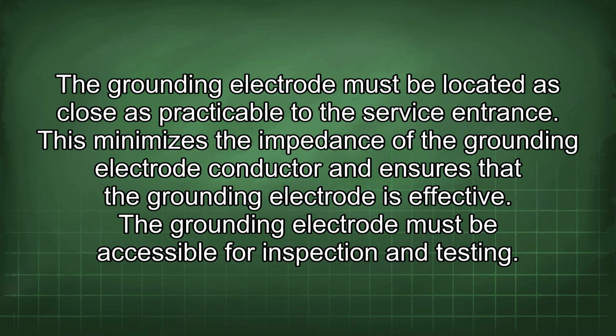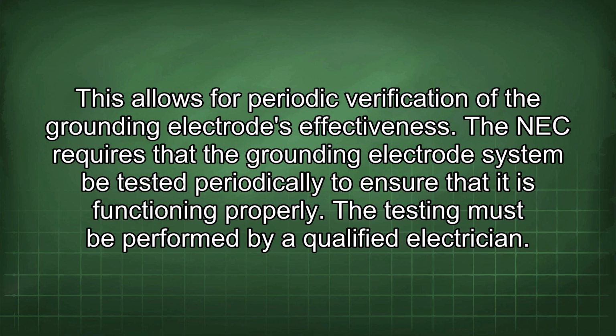The grounding electrode must be located as close as practicable to the service entrance. This minimizes the impedance of the grounding electrode conductor and ensures that the grounding electrode is effective. The grounding electrode must be accessible for inspection and testing. This allows for periodic verification of the grounding electrode's effectiveness.